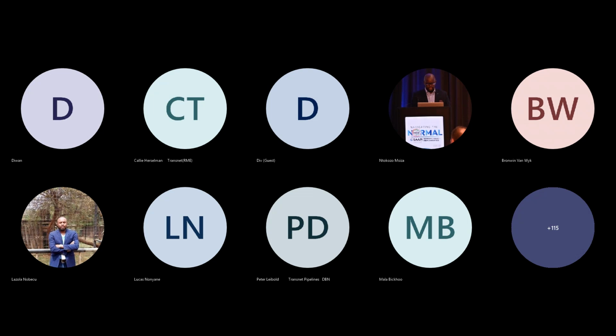Thank you very much. Maybe you can attend to when is the uncertainty acceptable? Oh, yes. When it comes to the uncertainty part, we cannot really say your uncertainty is unacceptable. Remember, the uncertainty comes from the traceability chain. The traceability chain starts with an SI unit or a primary standard. Then it goes down to another level of a secondary standard or a national measurement standard. And it further goes to the accredited lab and eventually to your end user, which might be the industry. So as the chain goes down, the uncertainty increases.